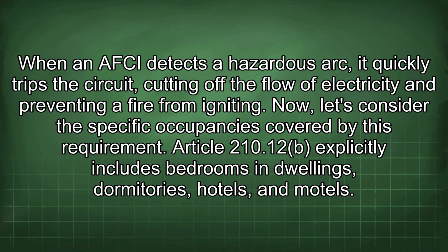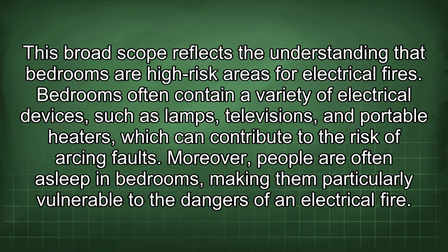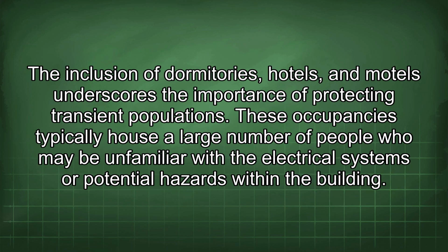Now let's consider the specific occupancies covered by this requirement. Article 210.12 explicitly includes bedrooms in dwellings, dormitories, hotels, and motels. This broad scope reflects the understanding that bedrooms are high-risk areas for electrical fires. Bedrooms often contain a variety of electrical devices, such as lamps, televisions, and portable heaters, which can contribute to the risk of arcing faults. Moreover, people are often asleep in bedrooms, making them particularly vulnerable to the dangers of an electrical fire. The inclusion of dormitories, hotels, and motels underscores the importance of protecting transient populations.